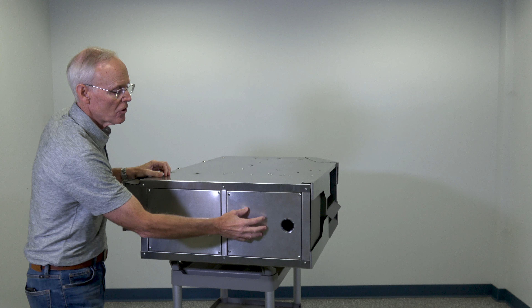But this negative regulator, neg-reg they call it, actually pulls the gas mixture in and mixes it up right here in the regulator, and then it goes into the heat exchanger. And it's pulled by the inducer through the heat exchanger. So this negative regulator is actually mixing it to the proper amount that it needs, and you really don't need any altitude correction.